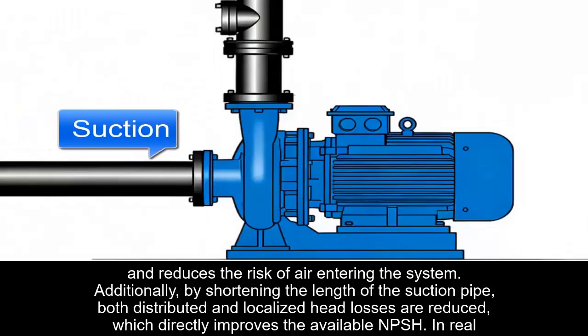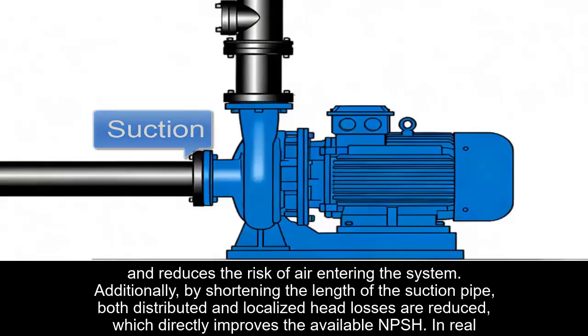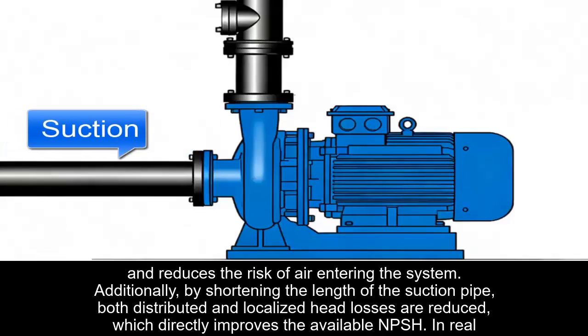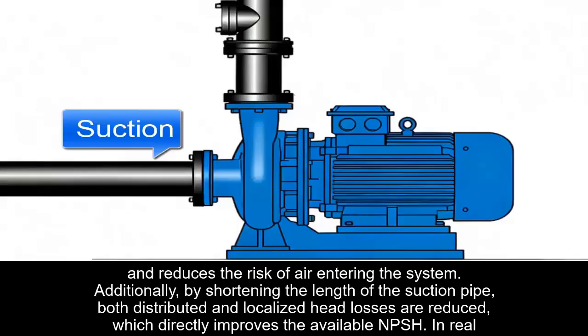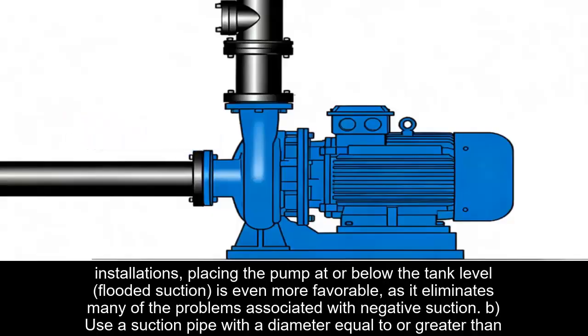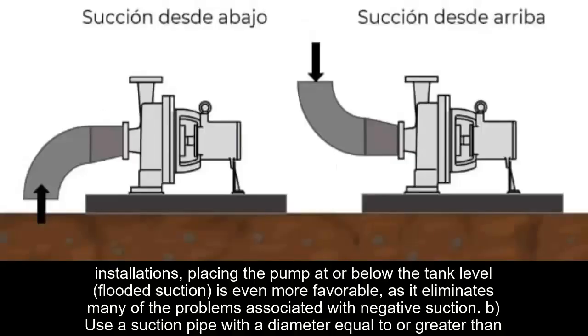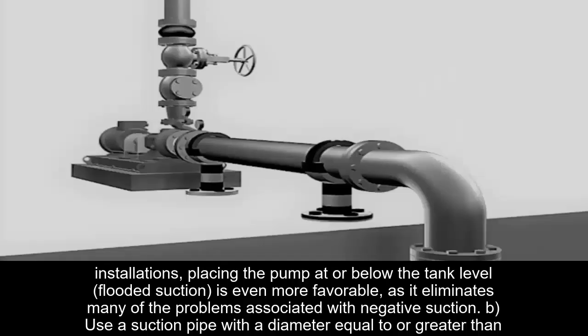Additionally, by shortening the length of the suction pipe, both distributed and localized head losses are reduced, which directly improves the NPSH available. In real installations, placing the pump at or below the tank level, flooded suction, is even more favorable as it eliminates many of the problems associated with negative suction.